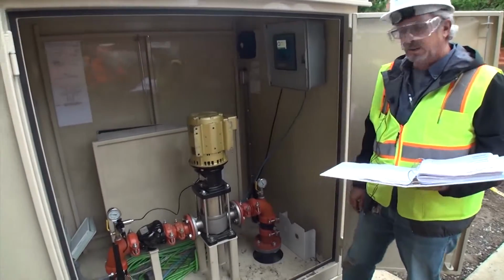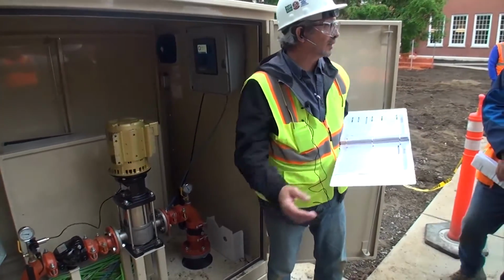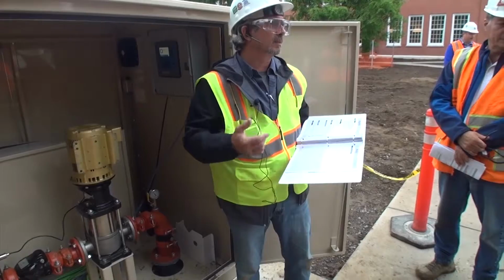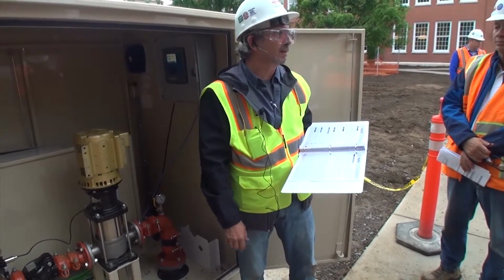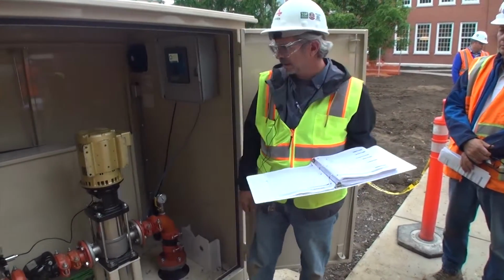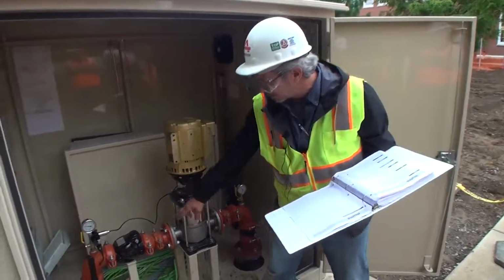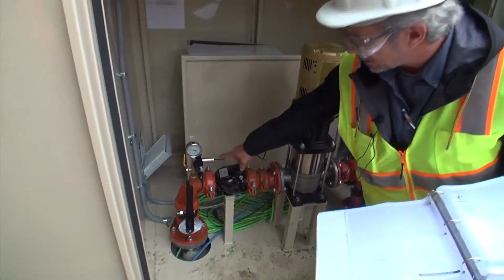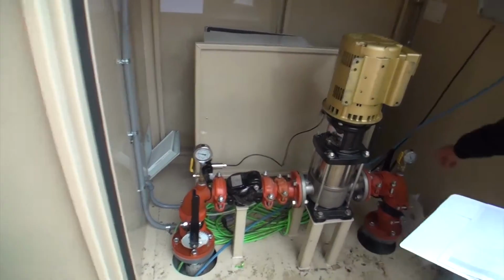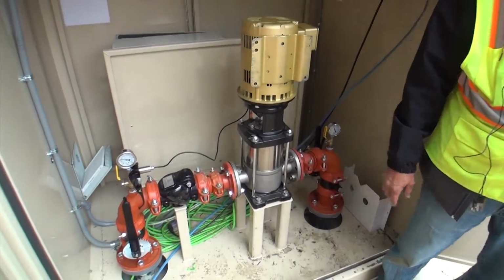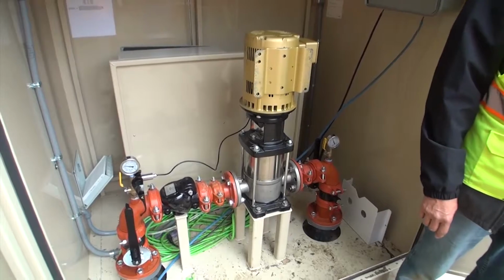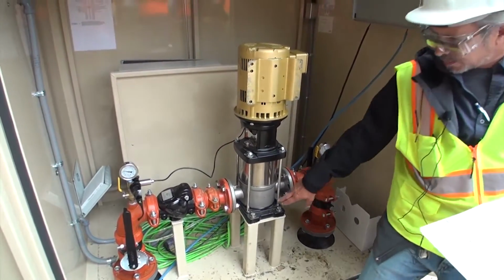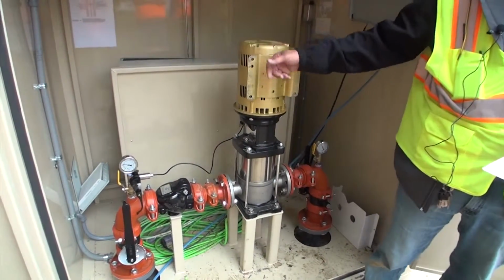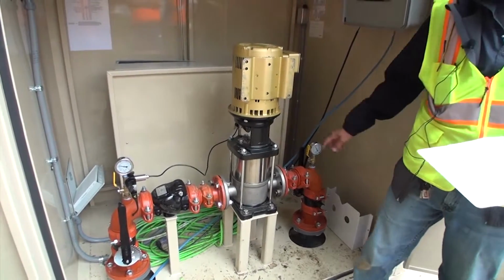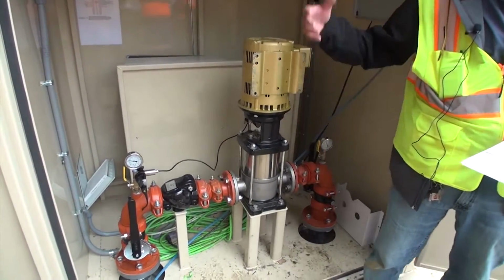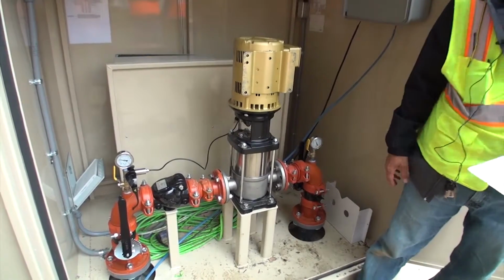So for winterizing in this particular station, you guys have to drain all the lines out in your field. You usually have a compressor out here and you blow it out. There's various ways you can do it, but the things I need to bring to your attention is this is the check valve, this is the transducer, and these gauges and this pump are all the main things you have to be concerned about with freezing. So there's a plug on this pump. You'll want on the other side. You'll want to pull that to drain it. You'll want to crack this to let air in so the water can run out.